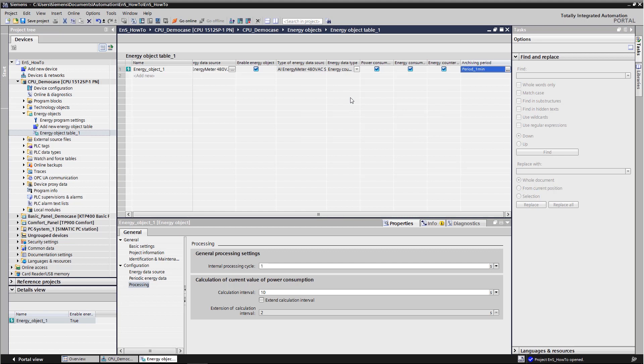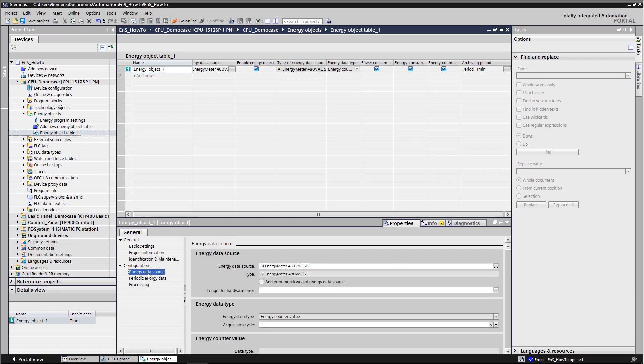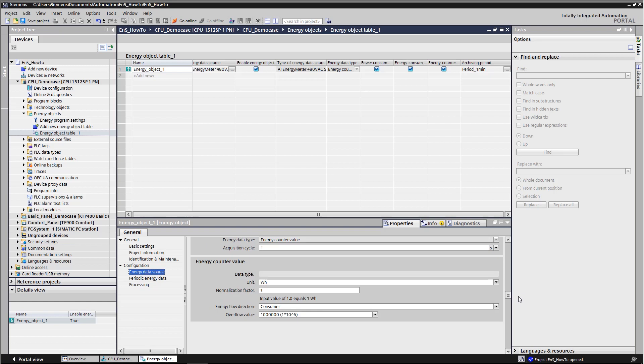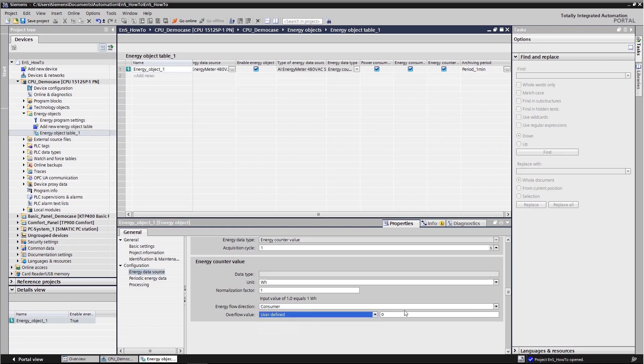We must adapt the energy meter overflow of the measuring instrument so that energy suite is able to respond to it. As no end value, count indefinitely, is selected in the energy meter, we have to select a very high value here. We enter 10 to the power of 15 under user defined.